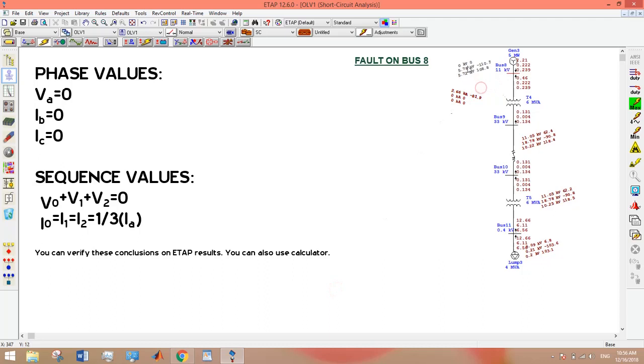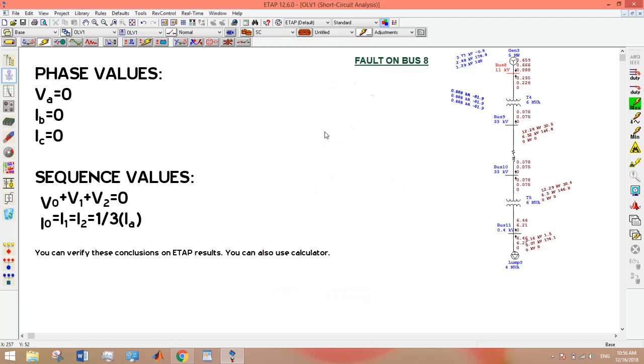You can verify these findings here on ETAP. If you observe the voltages, the voltage of phase A is zero and the currents of phase B and phase C are zero. This shows the single line to ground fault phase values. If you check the sequence values, all of the sequence currents are equal in magnitude, and you can verify the relation I0 = I1 = I2 = one third of the fault current. The vector sum of all voltage sequence components will ultimately be zero.